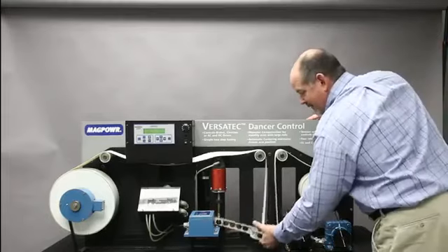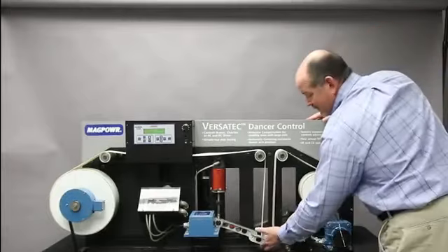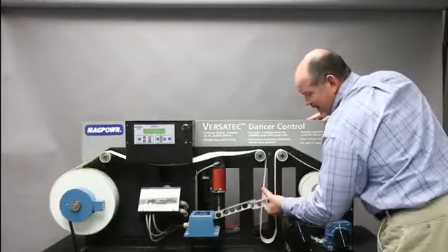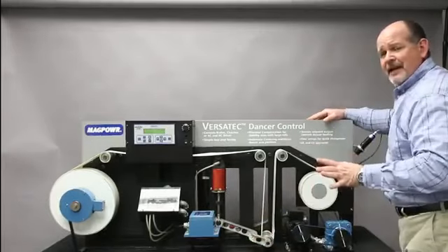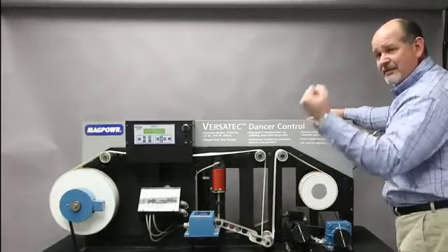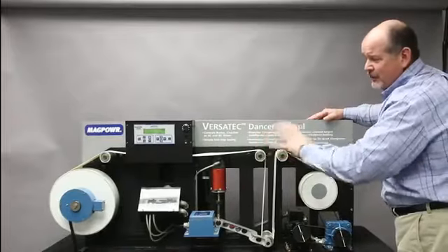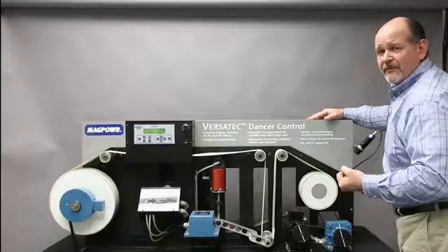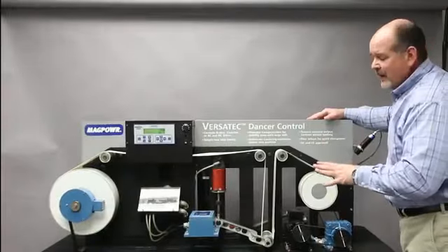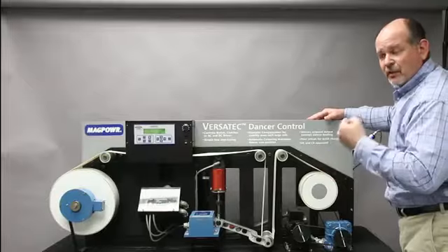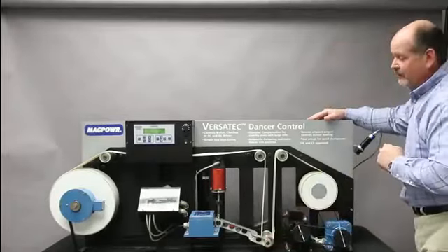Now this arm moves up and down. This is why it's called a dancer. It's supposed to move. So you can see that it's going through this full stroke, and we drilled these holes in it to take as much mass out as possible, because sometimes due to spikes or transients in the web, that arm may have to move faster or slower. And we want to make it as light as possible, or as low mass as possible, to take the inertia out of it, so we're not introducing tension transients or spikes with that arm.